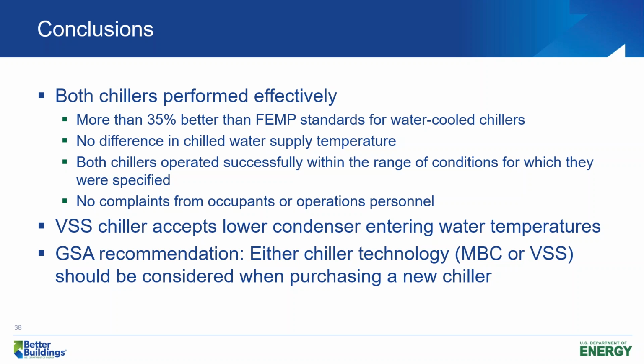One significant difference between the two is that the variable speed screw chiller has a wide range of condenser water entering temperature, so it can go from a low temperature up to a high temperature, whereas the magnetic bearing chiller can also do that, but it has to be special ordered for your operating conditions. So it's custom built, or custom ordered, for your operating conditions, whereas the variable speed screw chiller can just accept those lower and higher entering water temperatures.